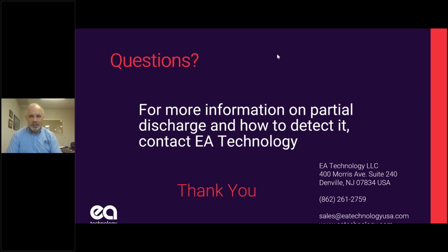Are HFCT, RFCT susceptible to magnetic field or other emissions? Because it's a toroid, unless you have an alternating magnetic field of a sufficiently high frequency going through the middle of the toroid, it won't play much of an effect. Our HFCT is shielded on the outside, and the toroid is really looking for current flowing through that hole in the middle. So you're not going to get a lot of that unless you're right on top of some very high frequency magnetic field generation equipment, like a motor or something like that.